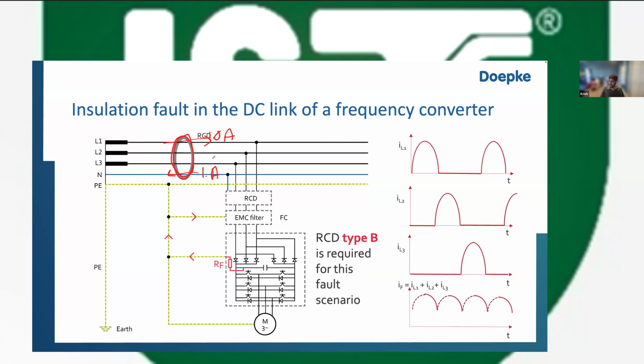But say for example, instead of 1.0 amp flowing through here and 1.0 amp coming out through here, you get 0.9 amperes flowing out. Then there is a net alternating current of 0.1 amperes, and that will induce a current inside this toroid. The type AC and the type A RCD work by using that current to cause the contact to disconnect. That is how a type AC RCD works.